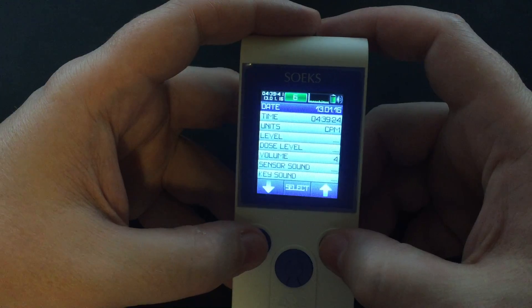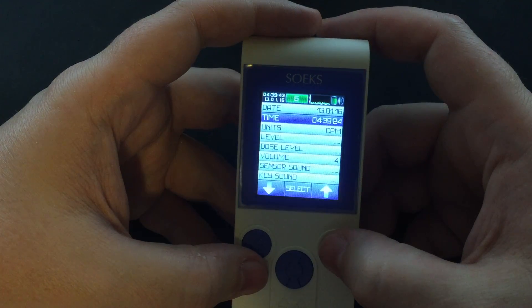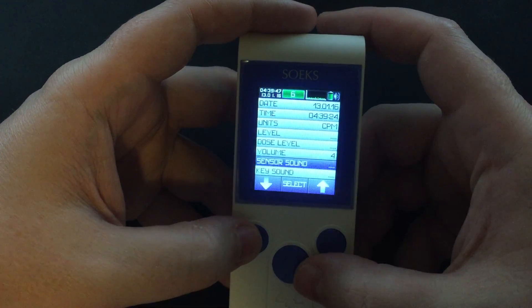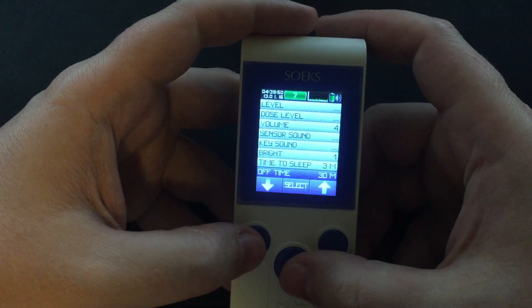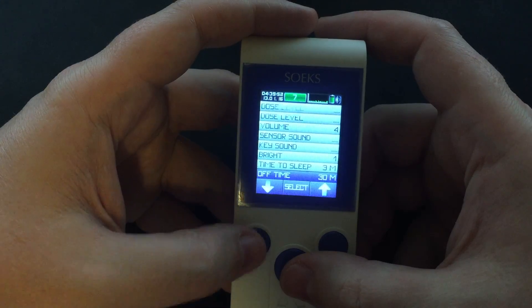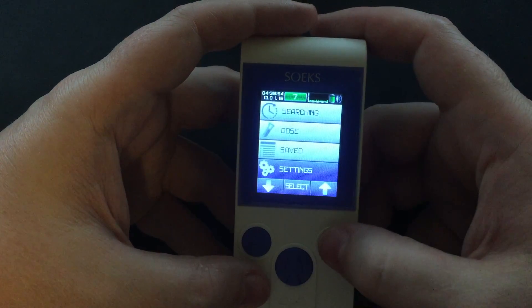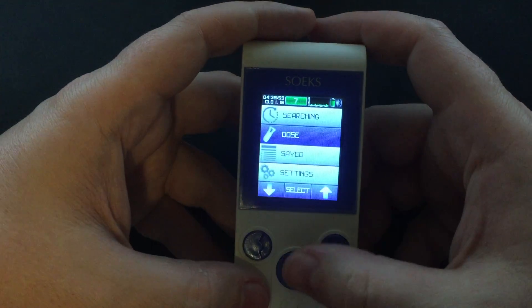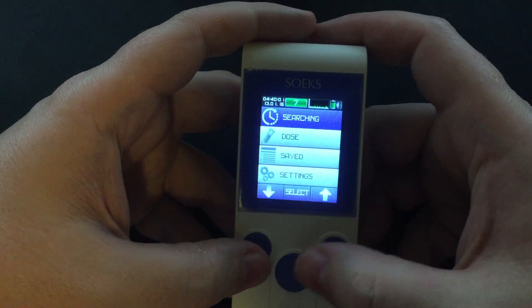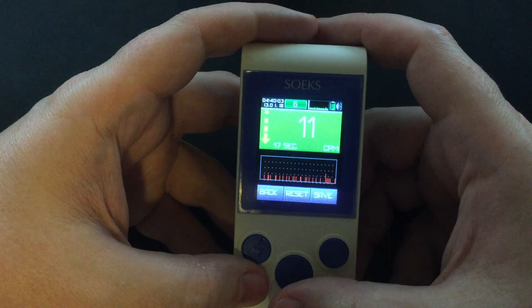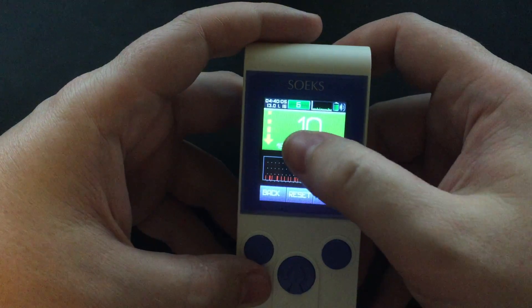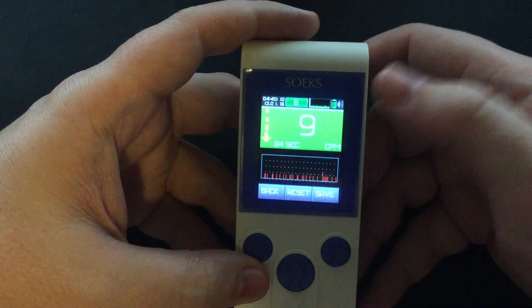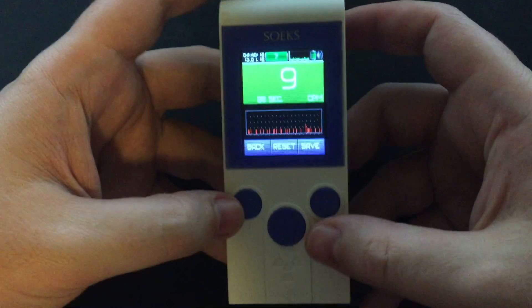You can see the day and time — I'm still up very early in the morning. Auto off time is 30 minutes. Dose mode is pretty simple — you can reset it. Search mode again updates much quicker than the primary sensor, so it lets you hone in on a source much more quickly.